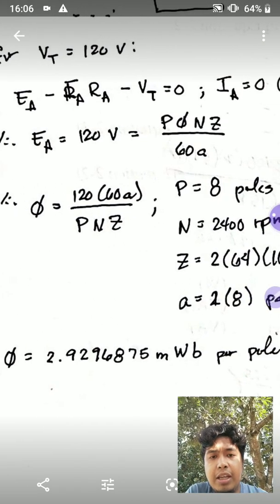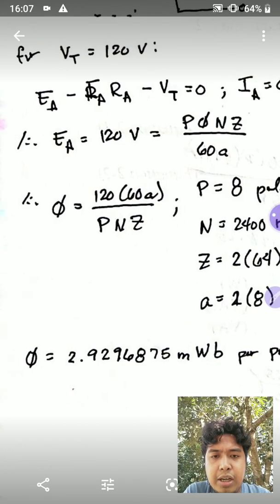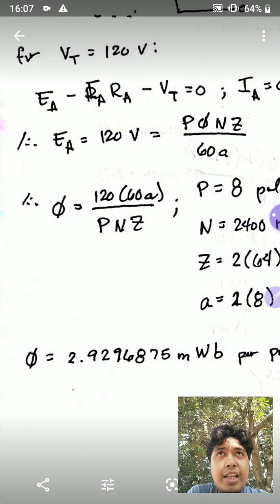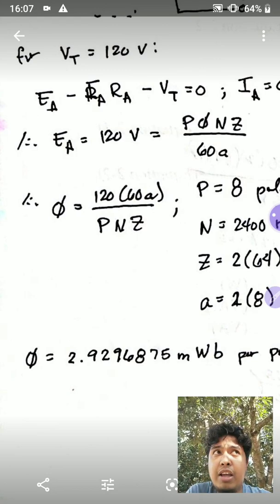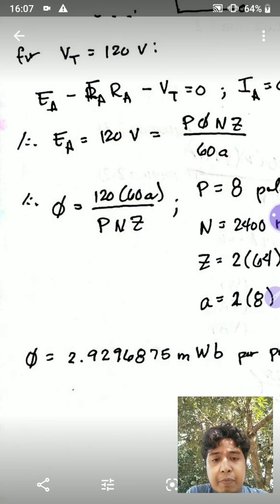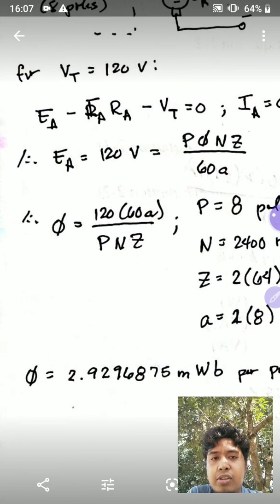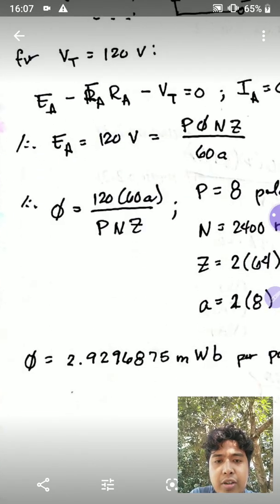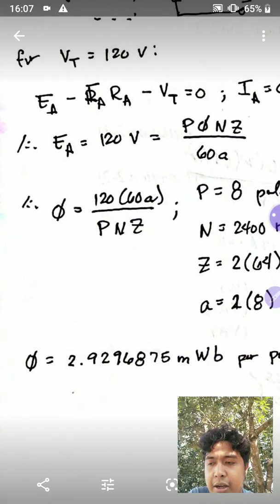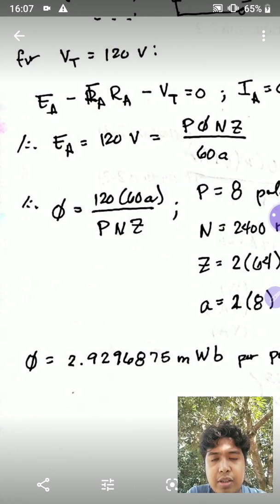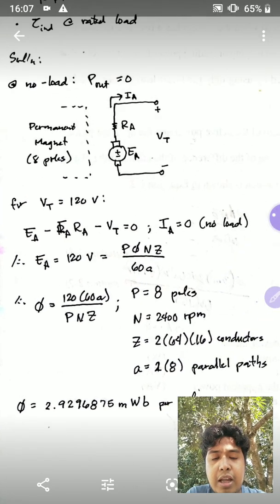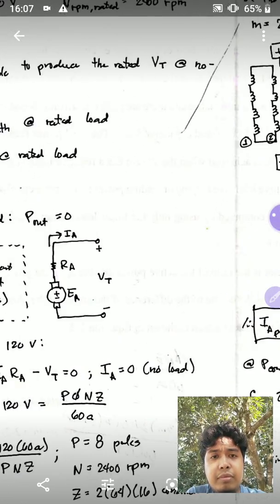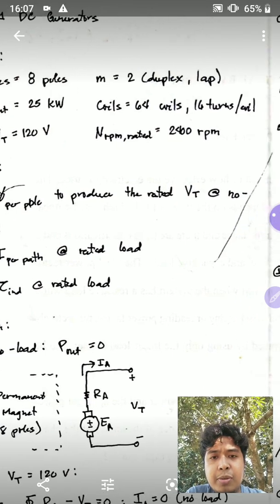If you substitute all of those values and solve for the flux per pole, you get 3 milliwebers per pole. That's basically how much flux should be present in each pole for you to produce 120 volts at the armature. Since this is a permanent magnet setup, you'll need a magnet with enough strength to produce this much flux.